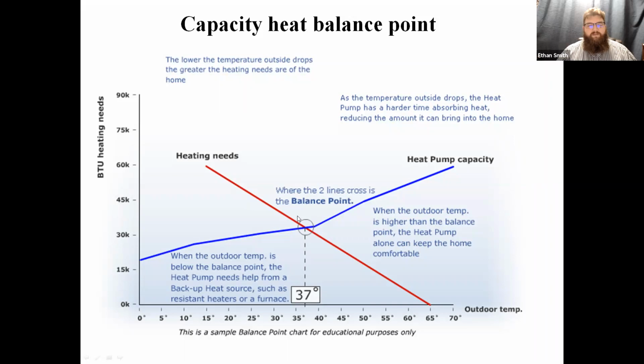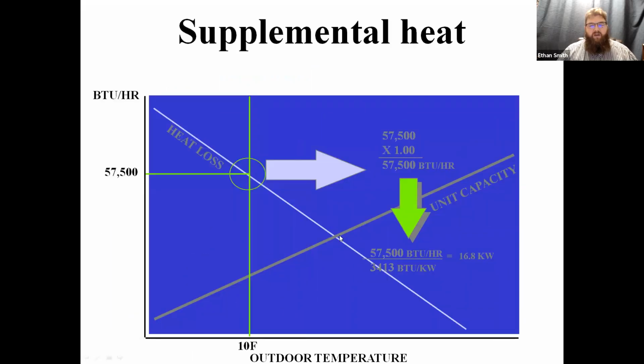Okay, so we can use a balance point like this to determine when I'm going to switch over to supplemental or auxiliary heat systems. So we know below 37 degrees on this system, I'm going to have to use supplemental heat of some variety, and above 37 degrees, I don't need any supplemental heat. So we can use that as a capacity heat balance point. So knowing that balance point, so there's my capacity balance point, we can look at the performance of the system and determine whether we want to bring supplemental heat on at that balance point or at various stages.